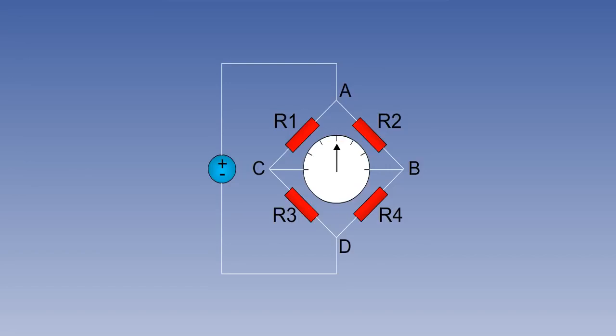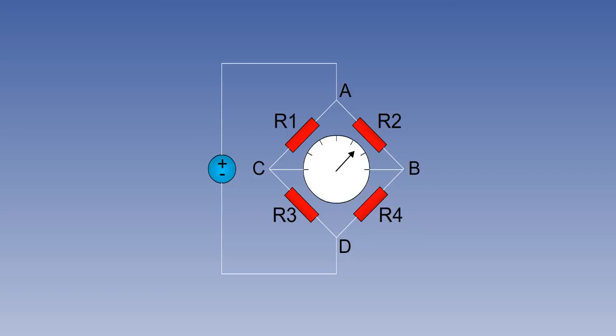We can see here a diagrammatic illustration of a Wheatstone bridge circuit. In basic form, the circuit consists of a power source and four resistors, labelled R1, R2, R3, and R4. For a given voltage input, the current flowing through the resistors will depend on the resistances. If the resistances are equal or balanced, the current flow in the circuit will be zero. If one of the resistors is exposed to the outside air, as temperature changes so will the resistance, causing an imbalance and a current flow proportional to the temperature change. This is an accurate system, and as it works on balancing resistances, any fluctuation in circuit voltage will not affect its accuracy.